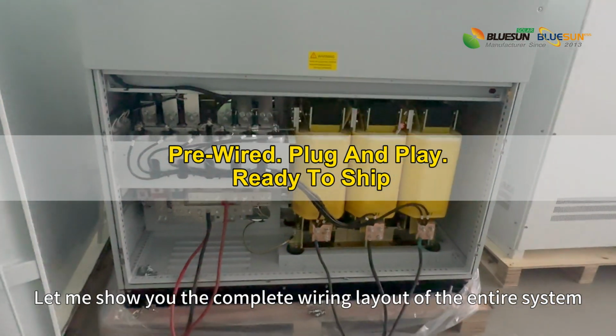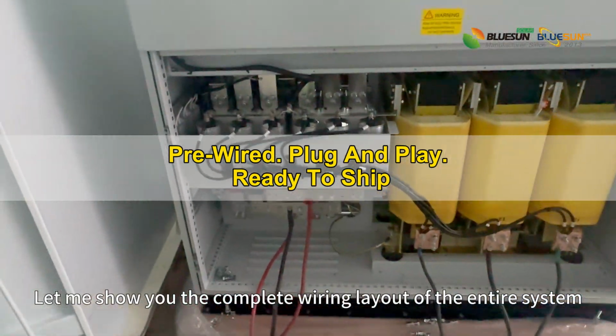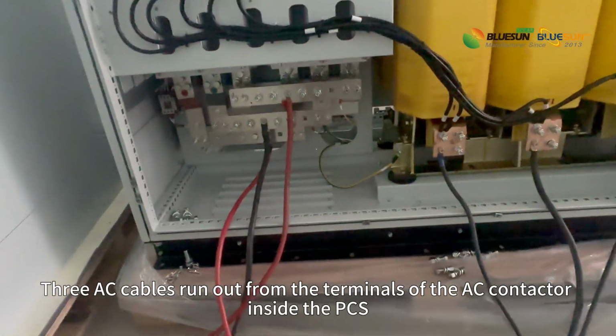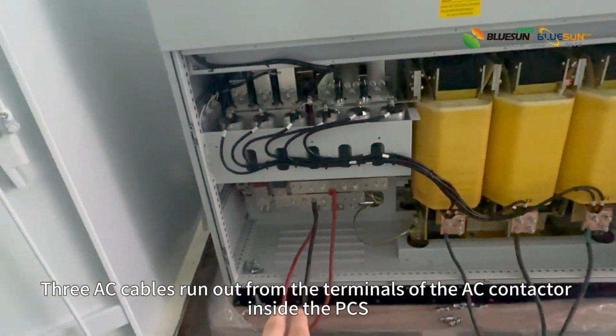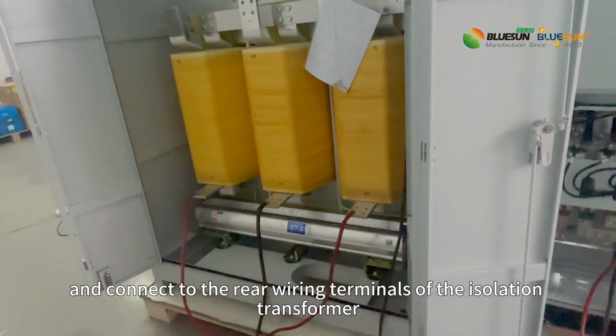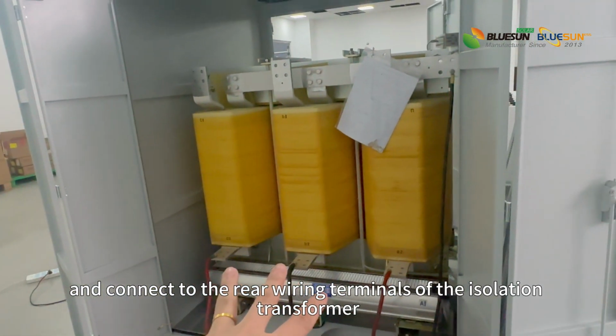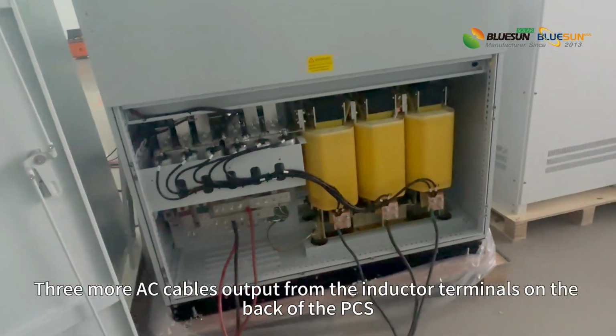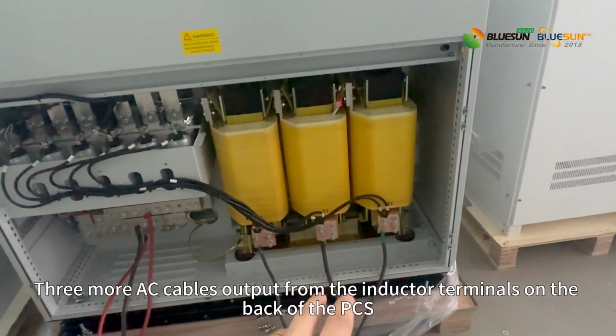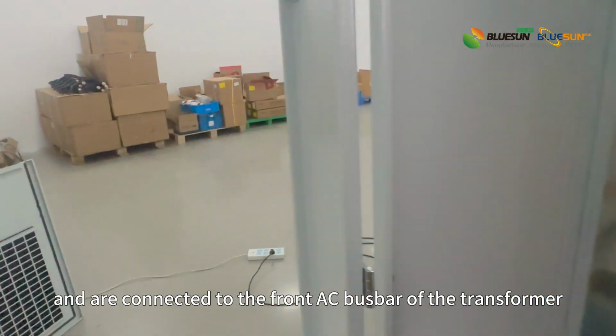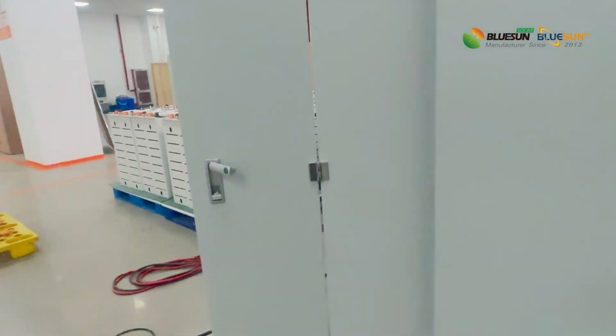Let me show you the complete wiring layout of the entire system. 3 AC cables run out from the terminals of the AC contactor inside the PCS and connect to the rear wiring terminals of the isolation transformer. 3 more AC cables output from the inductor terminals on the back of the PCS and are connected to the front AC bus bar of the transformer.